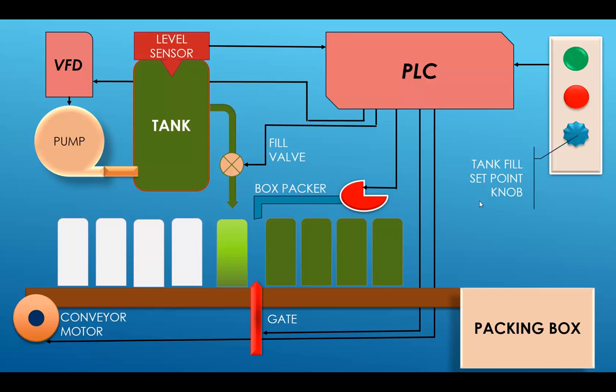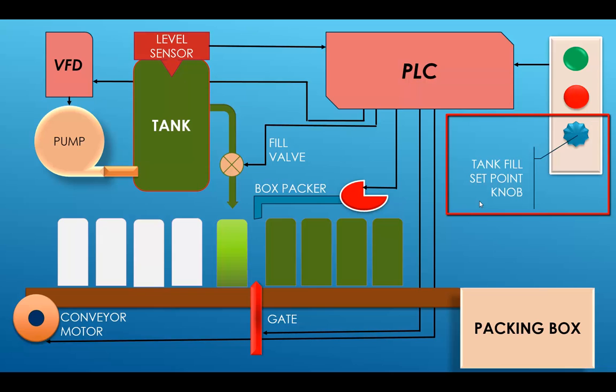Over on the right hand corner you have your inputs for start and stop of the process. And you also have your tank fill set point knob below those and you will set that knob from 0 to 100%. The PLC will read that as 0 to 1023 and again you will scale that back to 0 to 100%.